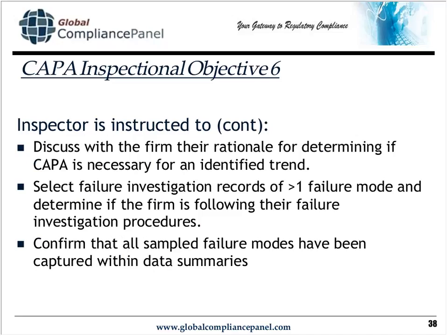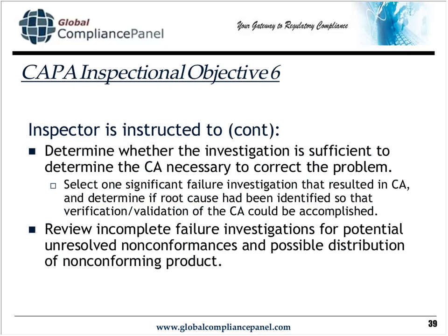And for every failure mode that they look at, when they sample these multiple failure modes, they're going to look at your data summaries and your trends to make sure that these sampled failure modes have been captured in there. They're going to look at whether your investigation was sufficient to determine the necessary corrective action. So they're going to look at one significant failure investigation. The way they determine significance of failure investigations is just one that resulted in a corrective action.